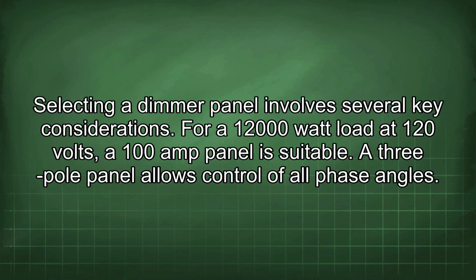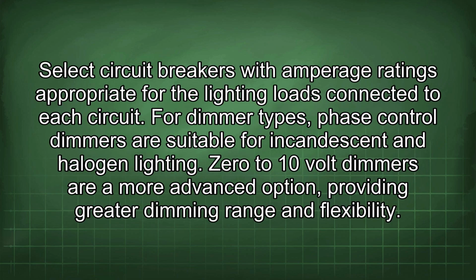Selecting a dimmer panel involves several key considerations. For a 12,000 watt load at 120 volts, a 100 amp panel is suitable. A 3-pole panel allows control of all phase angles. Select circuit breakers with amperage ratings appropriate for the lighting loads connected to each circuit.